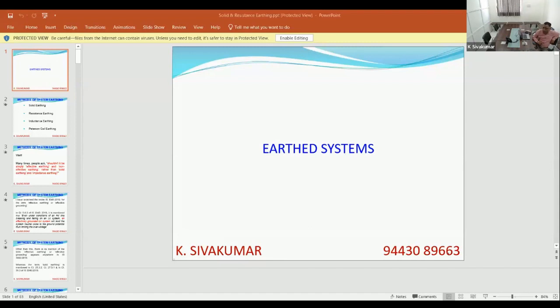That is the guideline given. That is the only known standard for grounding of sensitive electronic equipment, IEEE 1100, which does not advocate isolated earthing. Yes, actually, I would like to add here, there are some IEC standards as well, ISO IEC 30129, on earthing of all the sensitive electronics. So basically, now connecting both power protective earthing and the functional earthing to the earth grid is already out. Both have to be connected to the MET, the main earth bar. These clarifications are also there in IS 732 and in the NEC. So some clauses were given. So basically making it separate is a myth, as Shivakumar sir told.